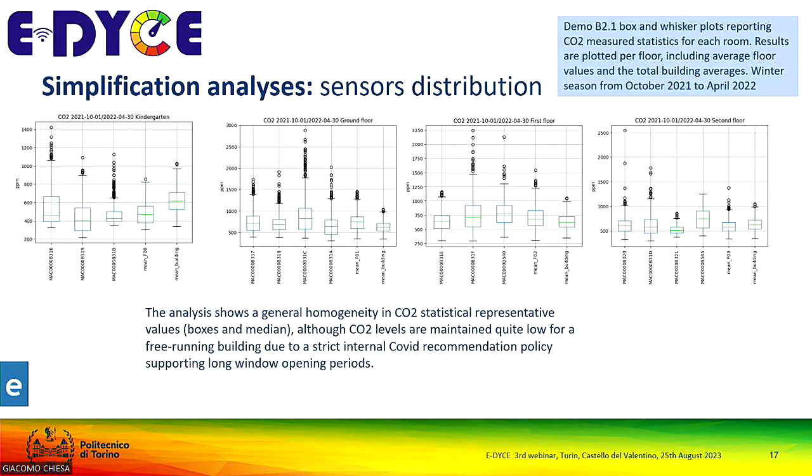in the building, in the residential, it is not like that, okay? In residential, we identify night and day schedules, and that clearly requires at least 2 sensors, one for the 2 parts of the building. Otherwise, we cannot really detect the behavior that arises there. But from the school point of view, since the usage is in some way scheduled, we can detect that classrooms have a sort of average approach, that they follow the same master control logic.